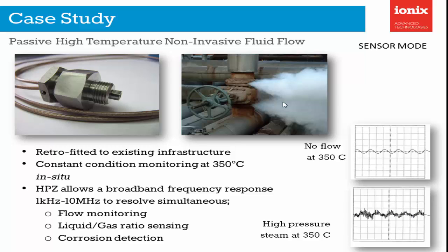So we developed a system, there's a simple piezo in there that allows you to put this directly on a steam pipe, and this is just some simple provisional data that we're able to show. You can suddenly pick up the steam. So the customer does, this is just AC noise, but when you've got the steam going through, you get a lot of extra signal, Fourier transform on that, and lots of complex analysis allows you to convert that directly into a steam flow in meters per second.